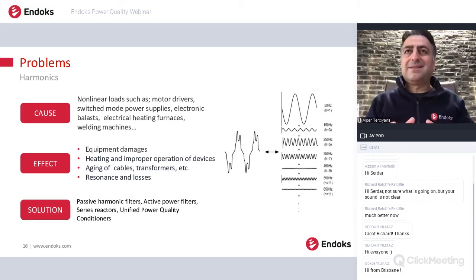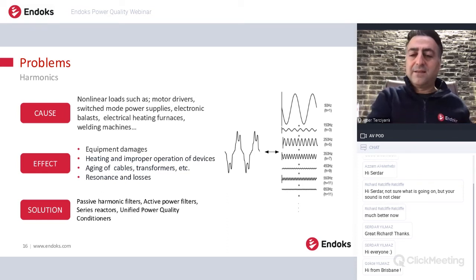So the resonance problem is very important because if the damping in the system, I mean the losses in the system, is not so much, this resonance problem can create bigger, higher voltage and current problems on the system. And for the solution to resonance, we mostly use passive filters, and we use active filters, series reactors, or unified power quality conditioners, first of all, in order to eliminate harmonics. If we eliminate harmonics, we eliminate the resonance risk.